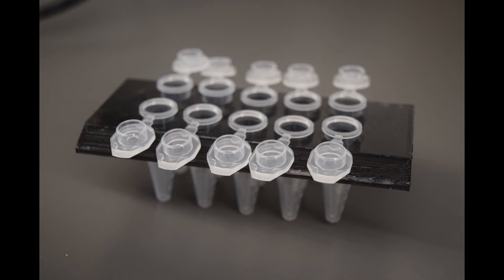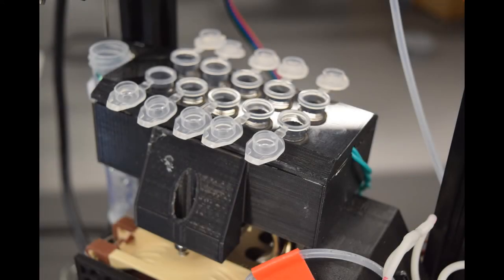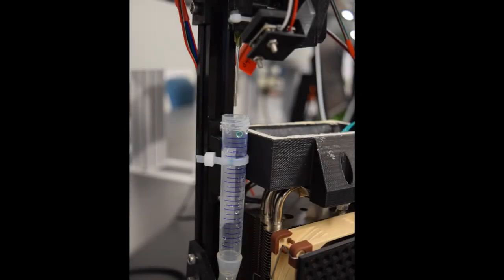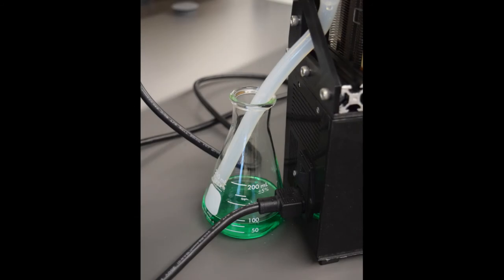Next, 10 microcentrifuge tubes are inserted into the sample block lid with their lids opening outwards away from the sample block. The lid is then placed on top of the sample block with the thermal probe between the two rows of sample tubes and the notch on the right side accommodating the thermal probe wires. If it's not already mounted, attach the waste tube to the waste bracket with a zip tie. The top of this should be at about the same level as the sample tube openings. Make sure to put a flask or bottle under the waste tube to collect the waste fluids.